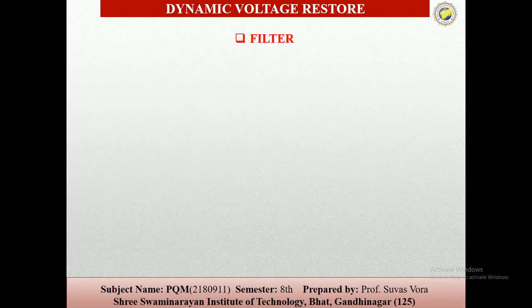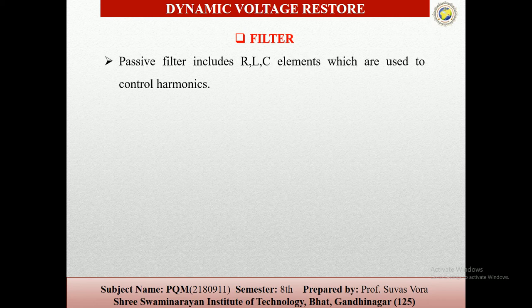Then after that, the filters. Basically the passive filter includes RLC elements which are used to control the harmonics. We know what a harmonic is. A harmonic is nothing but a multiple of the frequency of our power system. When multiples of our normal frequency are generated, harmonics are generated, and to remove them we generally use filters. Passive filters have RLC elements, and they are used to remove the harmonics in the current. The commonly used filter is the notch filter, which produces low impedance to specific current harmonics. So harmonic currents are sidetracked through the filter and the original path.